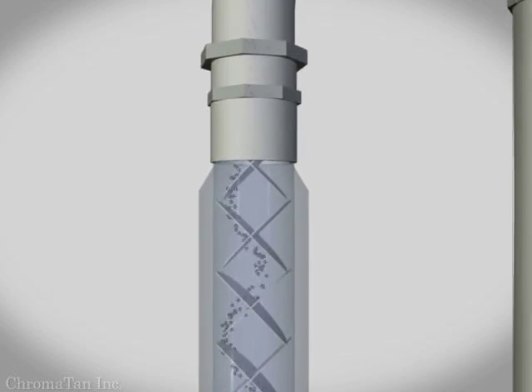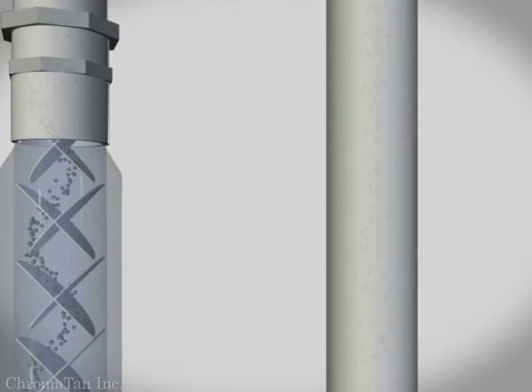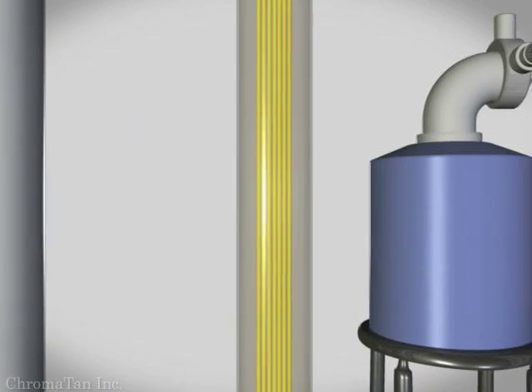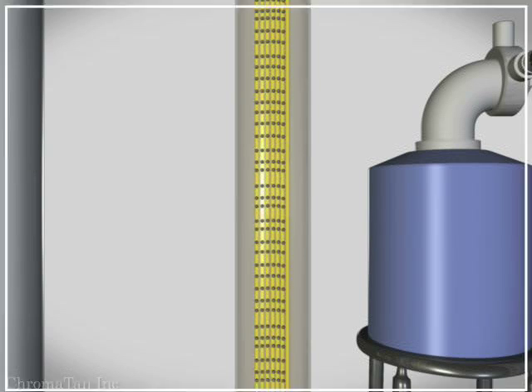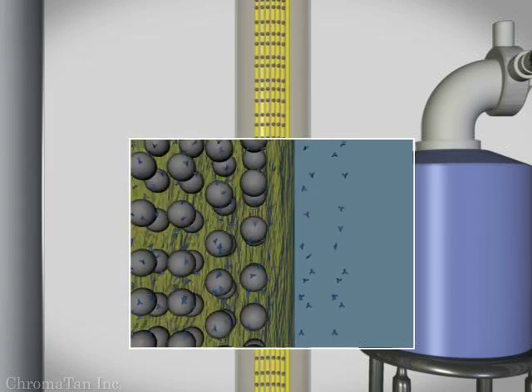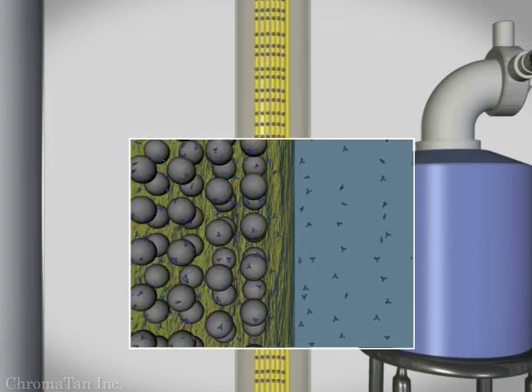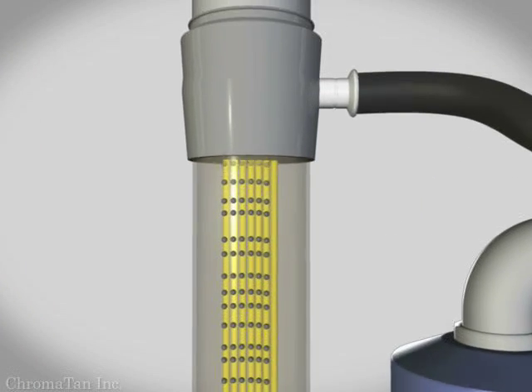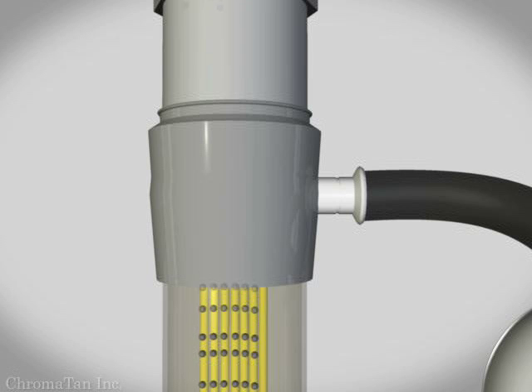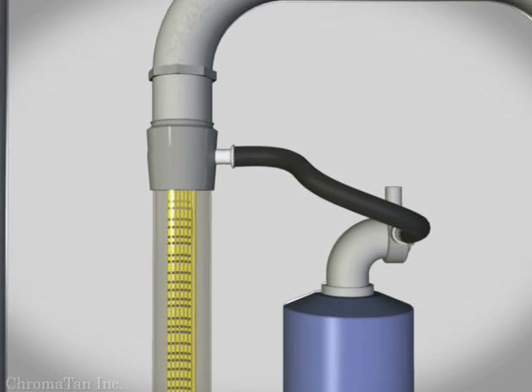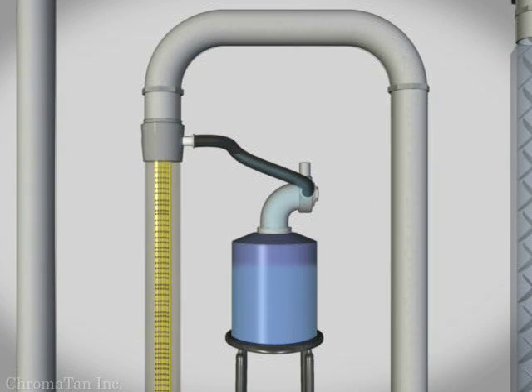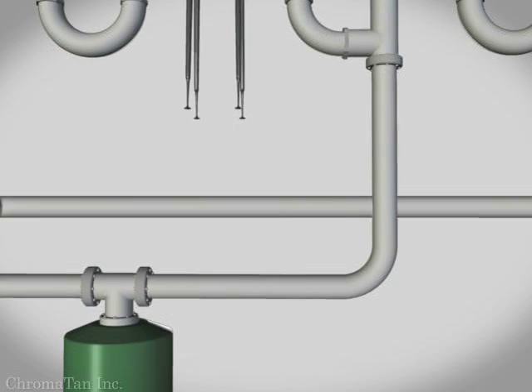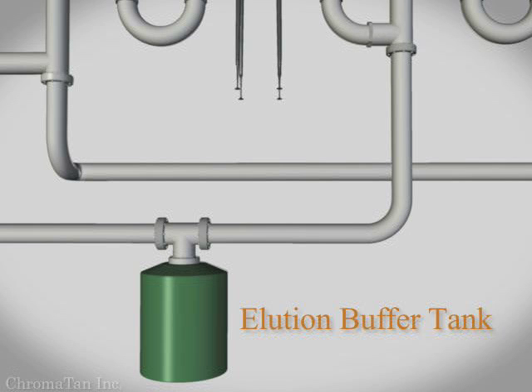The dilute slurry leaves the static mixer and enters the first hollow fiber module, whose purpose is to re-concentrate the slurry and separate the product molecule from resin particles. The module consists of a bundle of hollow fiber tubes with permeable membrane walls. The microporous walls retain resin particles, while the purified antibodies freely pass into the permeate side of the module. The re-concentrated slurry continues to the second stage of the CTC system, while the purified antibody is collected as product from the permeate side of the hollow fiber module. By itself, the first stage of the system can recover up to 85 percent of the product antibody.